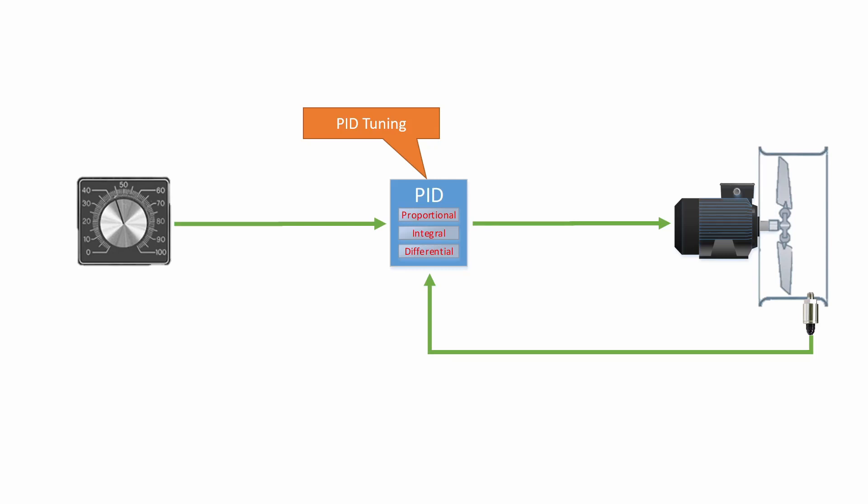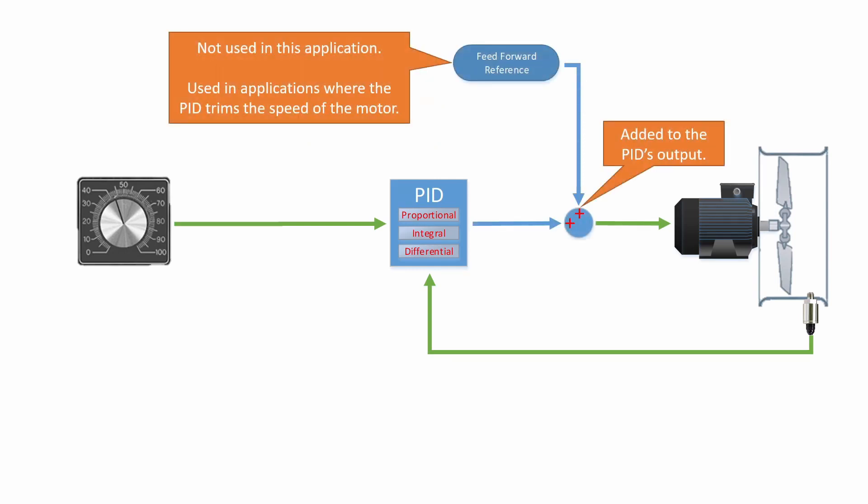All three of these are used to tune the PID. Most systems don't use differential, and only use proportional and some integral. In order to set up our system to accomplish our goals, there is more to this PID that we need to talk about. On the output side of the PID, there is something called a feedforward reference. We will not be using it in this application, but it is used in applications where you don't want the PID to control the system 100%. You only want it to trim the speed.